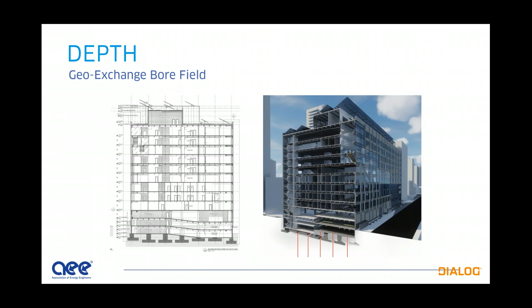Option one was to work in the mechanical pit, where there's a high overhead clearance where mechanical equipment will be located. Option two was to drill down vertically from the existing parking levels. And option three was to start at grade level outside the building and drill vertically down or diagonally under the building. Option three ultimately was not pursued, as the cost and coordination required for drilling on a busy street was not feasible. So basically, we decided to go with options 1 and 2, both from the mechanical pit and from the parkade, drilling straight down. We have drillers now that have very compact drill rigs that specialize in drilling boreholes in existing parking garages and tight spaces, so they were able to drill these holes. Takes a bit longer, but 600 feet deep, as I said.